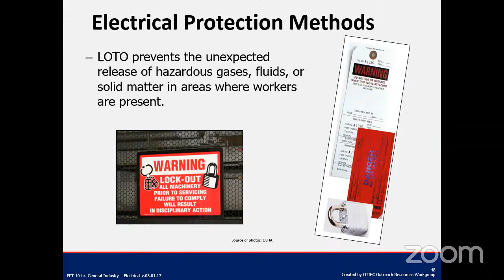Now, power source identification. Recently I've been to an audit for one of the companies in Solinganallur. The moment we open the control panel, we must have an idea what this control panel caters for, equipment A, B, C, D. There has to be some link. The control panel must have some kind of layout so that the operator knows where to go and switch it off. If there is any problem and I have 10 machines, and the panel doesn't have any marking of where I am going to switch off, what will I do for safety? I will switch off all 10.